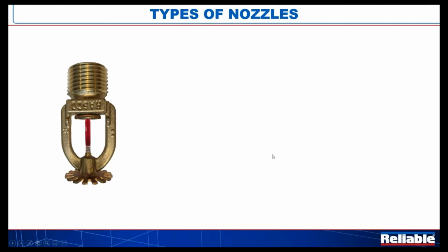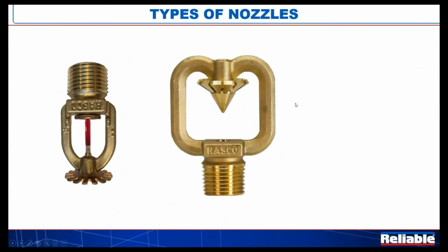And then the other types, and by the way, NFPA 15 essentially says that you use open nozzles for protection. But similar to what we have in NFPA 13, there's a section that says where approved, sprinklers shall be permitted to be used in these systems and installed, and this is the important part, installed in positions other than anticipated by their listing. So what does that mean? You knock the guts out, and all of a sudden, does this sprinkler have to be pendant anymore? No, it doesn't. Because now it's a nozzle, it can be oriented in any position that's needed to accommodate the protection scheme. So sprinklers, low velocity nozzles, medium velocity nozzles.